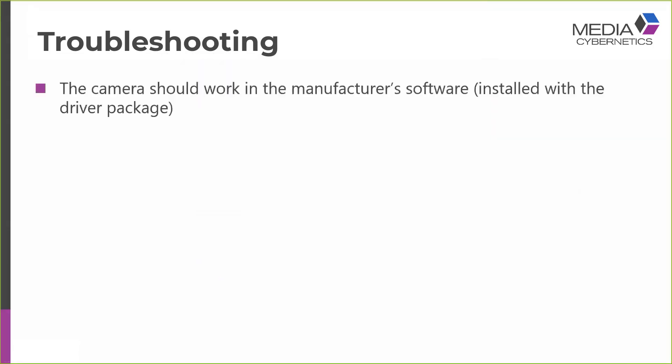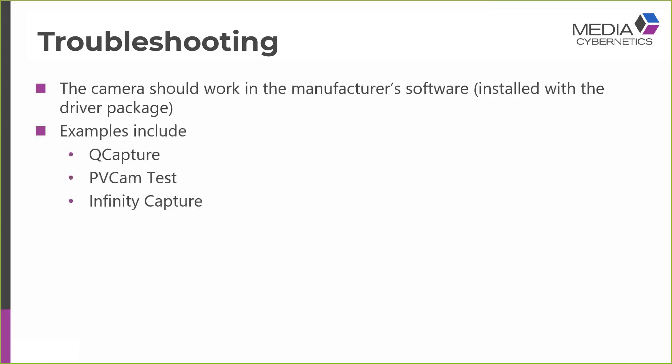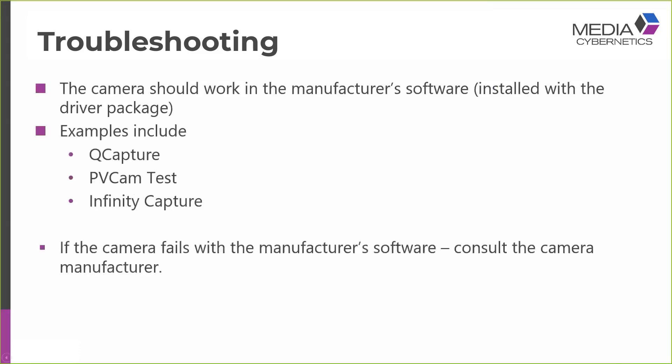The next troubleshooting step you might want to take would be to check the camera with the manufacturer's software. So the camera should always work with the manufacturer's software, and this is generally installed with the driver package. Examples of manufacturer's software include QCapture. This is QImaging's software. We have PVCam tests from Photometrics and Infinity Capture for Lumenera cameras. If the camera fails with the manufacturer's software, it's probably wise to consult the camera manufacturer and see if you can figure out what the problem is.